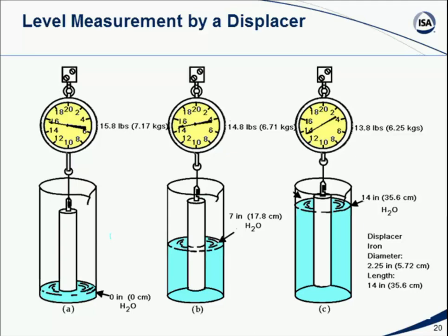What we've seen is that we can make a level measurement. We can tell that the level of water in this tank is between 0 inches and 14 inches based on the weight that we're measuring varying from 15.8 pounds to 13.8 pounds. So as the water level goes up, the hanging weight goes down. We have a 2 pound weight difference that is an indicator of a 14-inch difference in the level in the tank. So by watching the differential in the hanging weight of this displacer, we can make an inferential determination of the level in the tank.